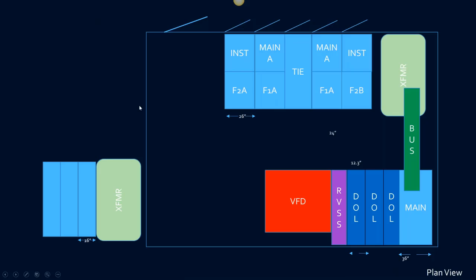So what does the e-house do to our room? Well, it reduces the size even further because now we have these doors on the back of the house, and this is our access door. And now, whether we are front connected or rear connected, we have eliminated the need for the rear clearance, because basically the gear comes to the e-house manufacturer without doors on the rear, and it's integrated into the e-house, and then the e-house door becomes the switchgear door.